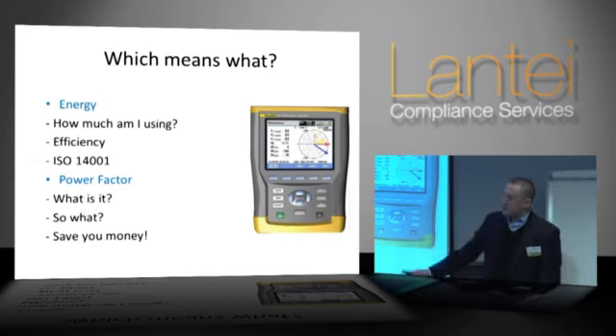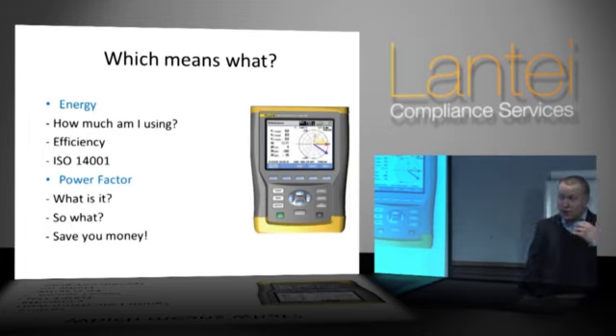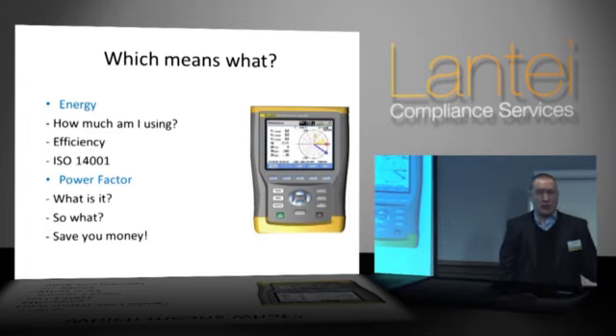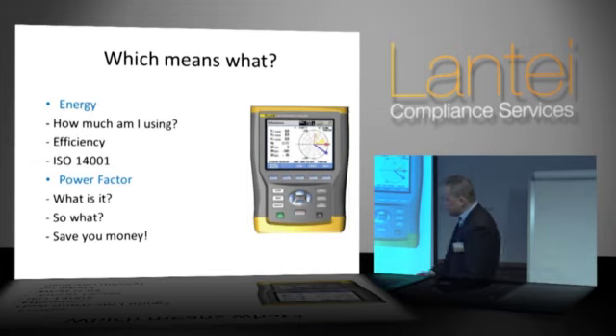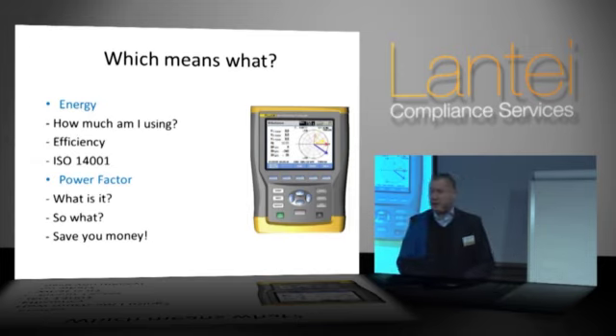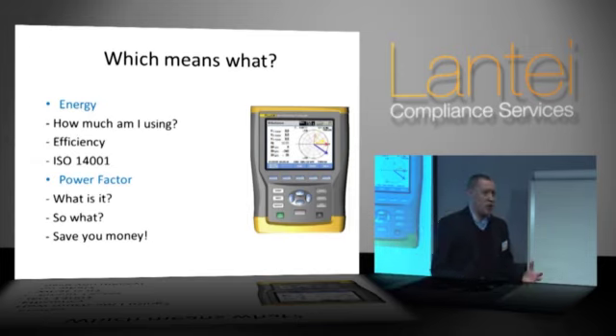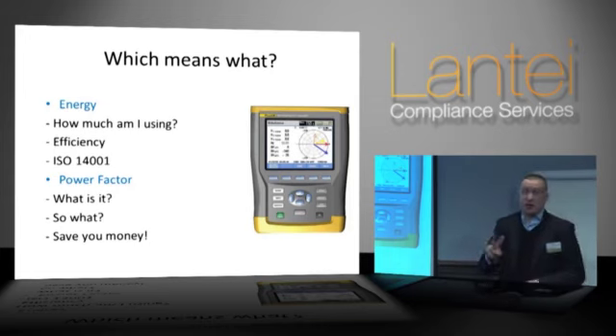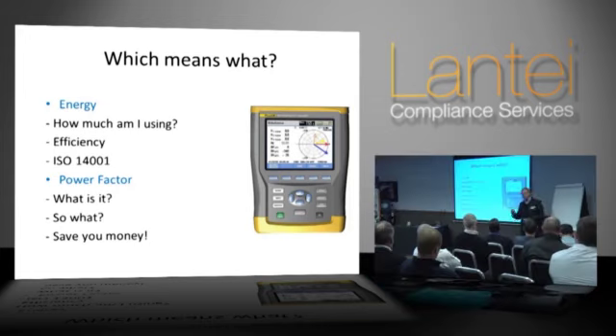When we talk about efficiency, specifically we're looking at whether or not we've got power factor issues within our electrical installations. For those who aren't aware, certain types of electrical equipment actually need two types of power to make them work. First you've got what we call actual power - does what it says on the tin, it's the actual power that piece of equipment needs to physically work.